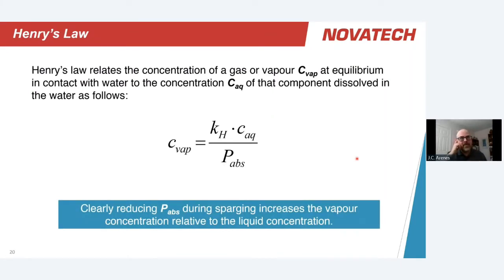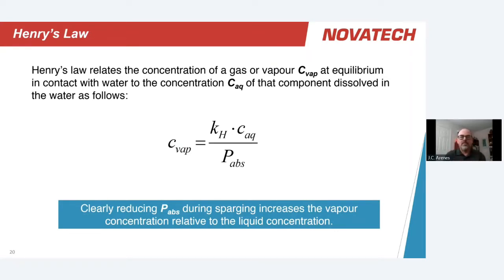A quick word about Henry's Law, which has guided the design of the Novatech sparger technology. In its most basic form, Henry's Law relates the concentration in the vapor phase to the concentration in the aqueous phase. What's most interesting is that the pressure the system is operated at is in the denominator — meaning that if we lower this pressure, we increase the concentration in the vapor phase. Since we're trying to pull hydrocarbons from solution in water into the sparge gas in the vapor phase, lowering the system pressure increases sparging efficiency.